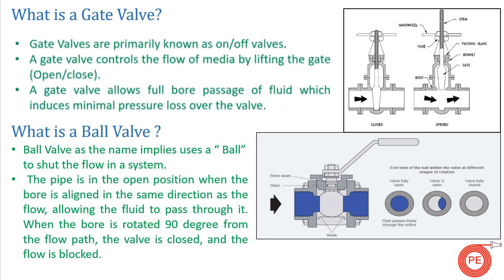So, what is a gate valve? A gate valve is the most basic valve we come across in our daily lives or in industry. Gate valves are basically known as on/off valves. When we want a quick close or quick open, or when we require isolation — that is, a complete shut-off in the system — we use gate valves. The gate valve uses a wedge-type system connected to a handwheel. When the handwheel is rotated, this wedge goes up and down. You can see the closed position of a gate valve. When the handwheel is rotated, the spindle goes up, the wedge goes up, and flow starts moving. It allows a full-bore passage for the fluid.